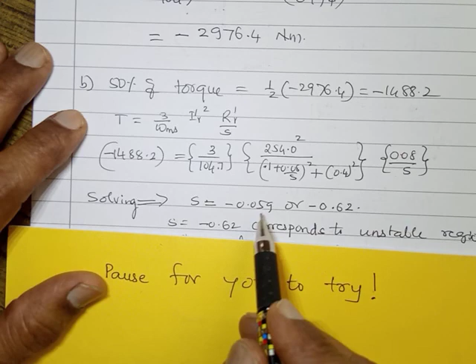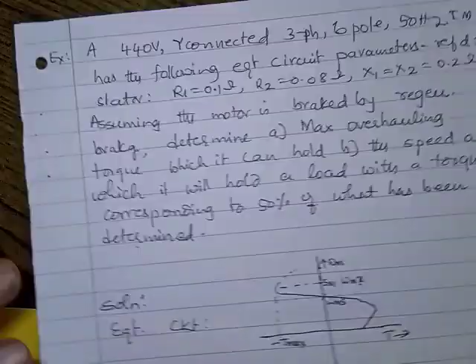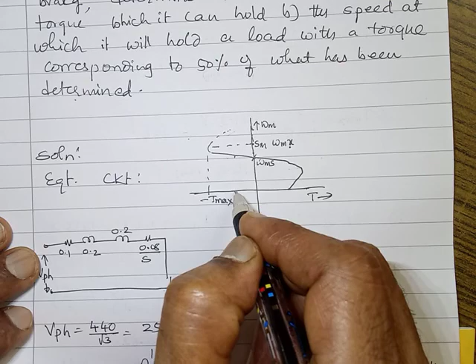Because Sm we got 0.194, anything more than this 0.194 will come somewhere here. This region is unstable region. That is why this 0.62 that we are getting is in the unstable region. We don't take that. Therefore minus 0.059 is the one we select. It corresponds to less than 0.194, that is, the operating point falls here. This is a stable operation. So we get S as this. After substituting this S in n equal to 1 minus S into ns, but S is minus, we will get 1050 rpm. So the 50% of braking torque we will get at 1050 rpm. ns is 1000, slightly more than this, somewhere here we will get half the maximum braking torque. Is it okay?